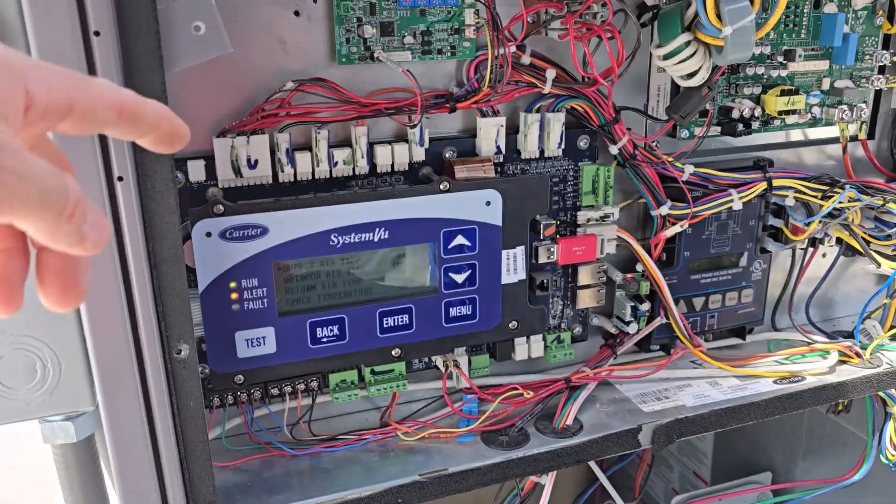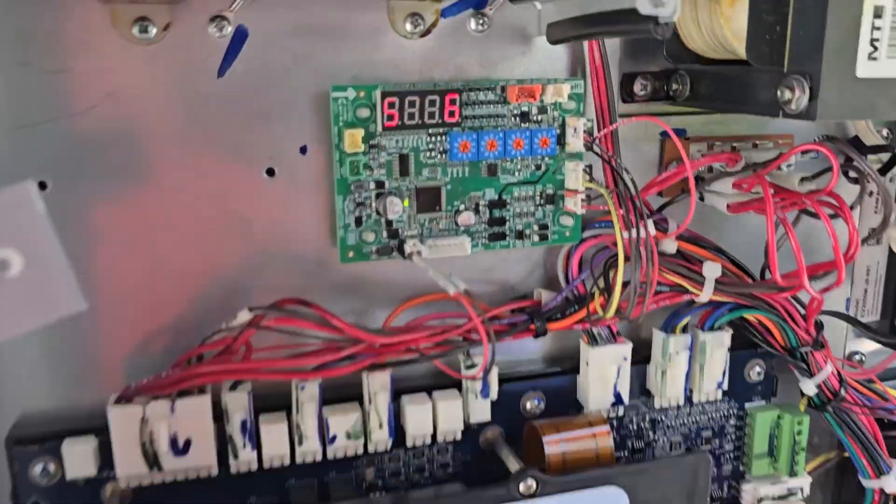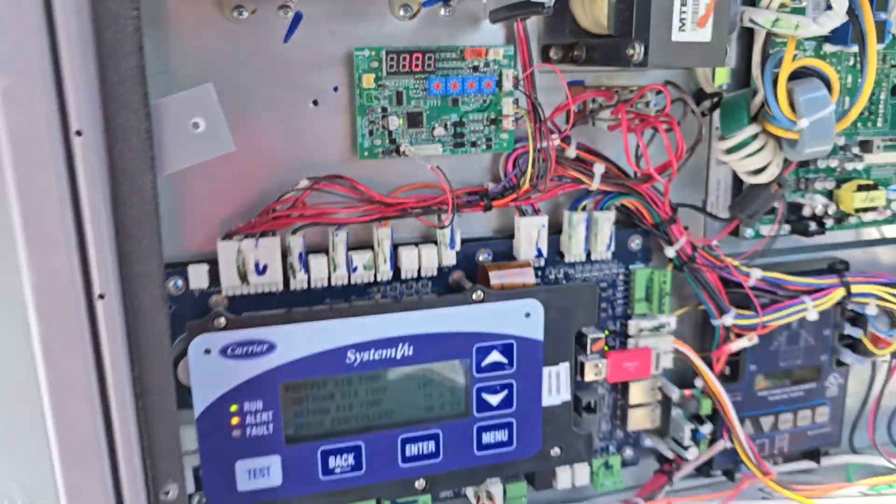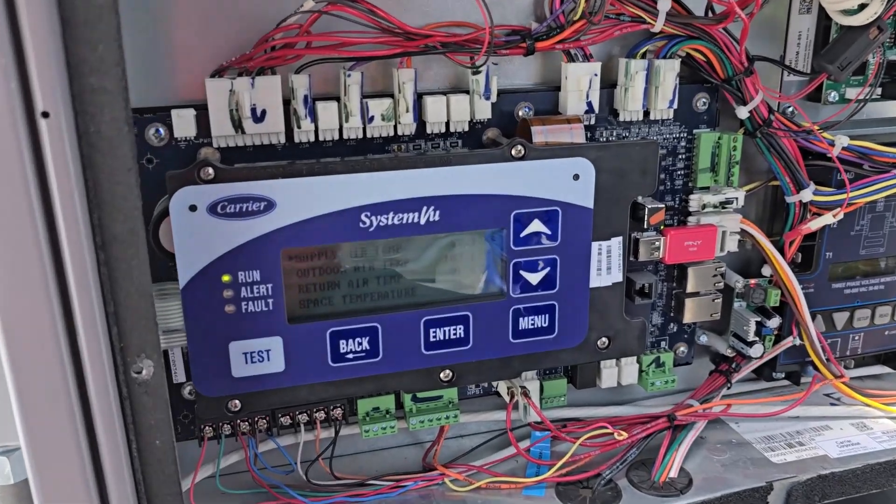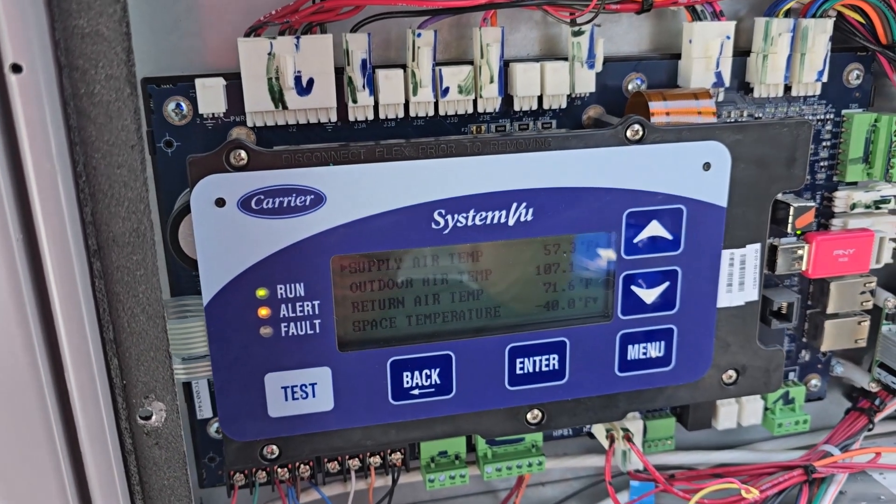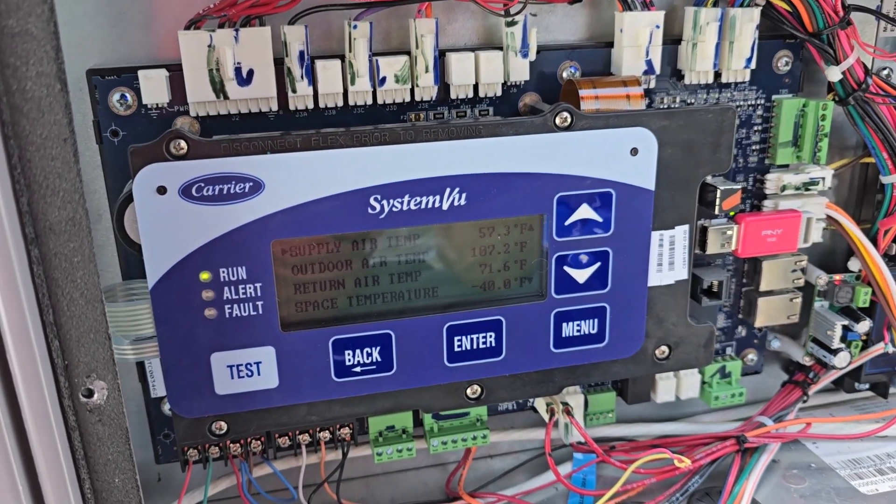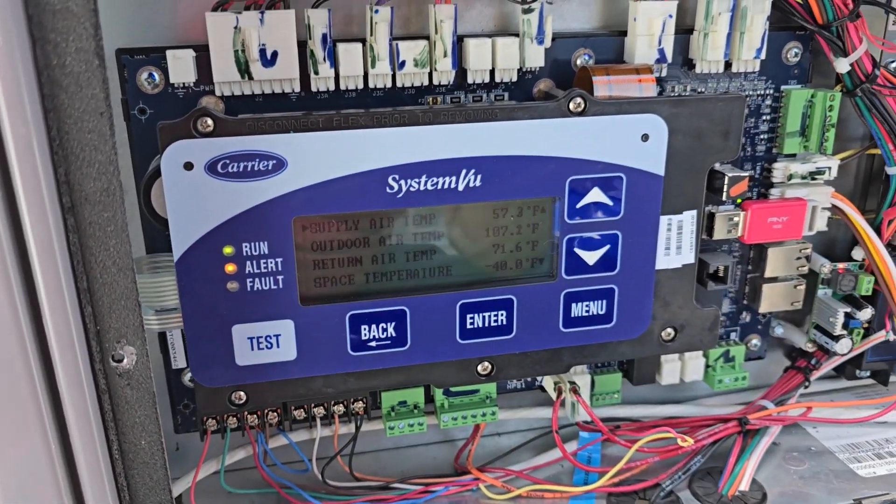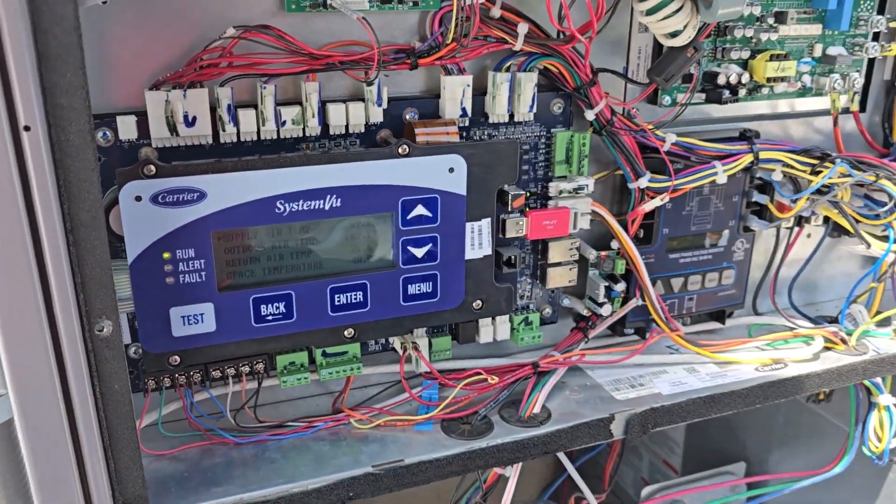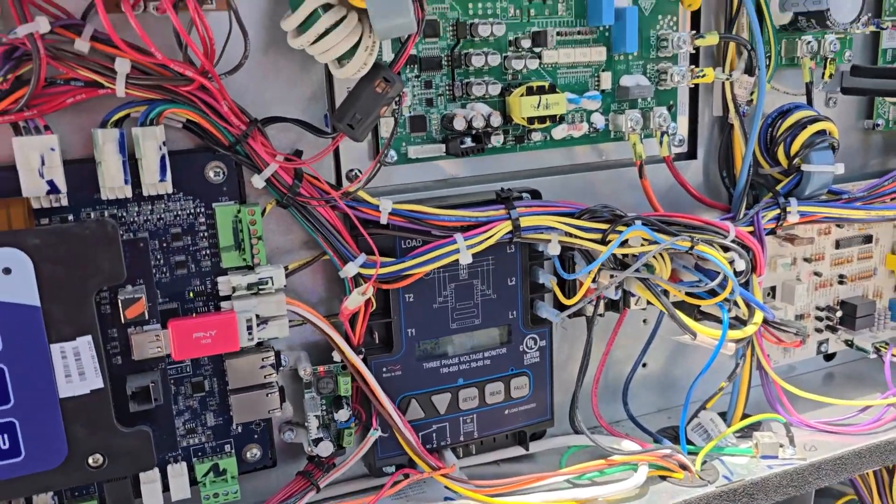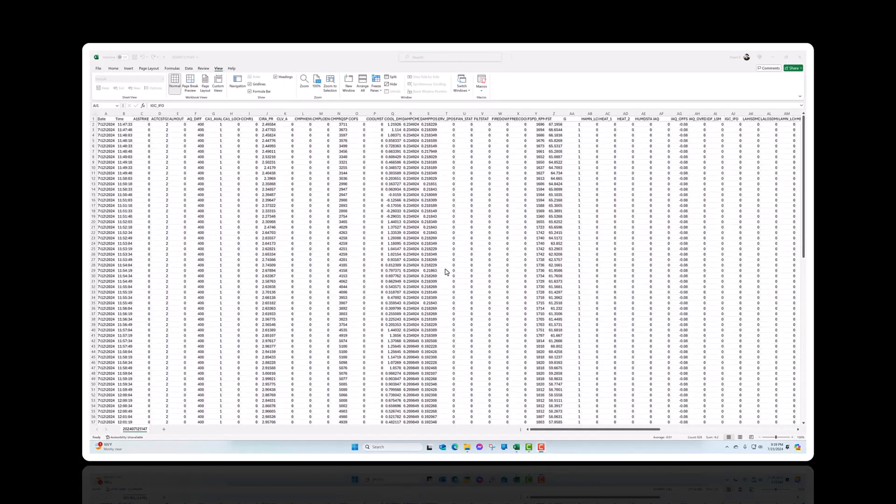So it's been running for like another 15, 20 minutes while I've been watching it. It's just pegged down at 5100 RPM. That's where I limited it. And it's got 71.5 return air. So it's dropped like four degrees. I think it was like 75-ish when we started it the last time. And it's 57 supply with 107 degree outside air. It's probably about 80 mixed air. So we're dropping about 22, 23 degrees. So it's working great. The phase monitor's happy. Everything's happy. Should be good to go.